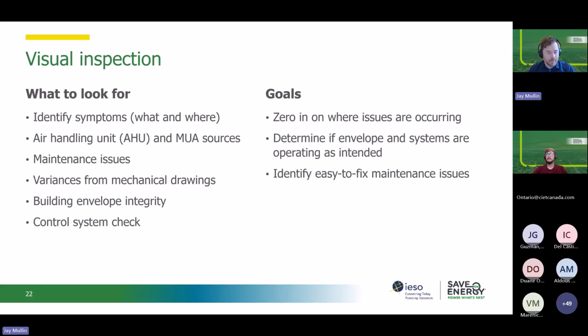Next part is the visual inspection. You want to identify those symptoms that we talked about, so doing a walkthrough, talking to operators, maintenance staff, and production supervisors, and looking at your air handling units or your makeup air units, confirming whether units are bringing in outdoor air or recirculating air. Sometimes units labeled makeup air units might actually be recirculating interior air, or air handling units that might be assumed to be recirculating could be bringing in outdoor air as well. So, looking at what's actually happening and at maintenance issues: are fans running, are filters clean, are dampers operational, is exhaust only running when it's needed during operational hours, are louvers blocked or closed, and are the exhaust and makeup air units running when expected?